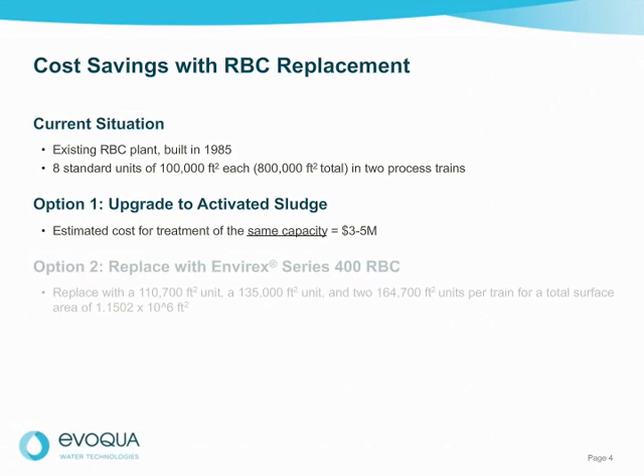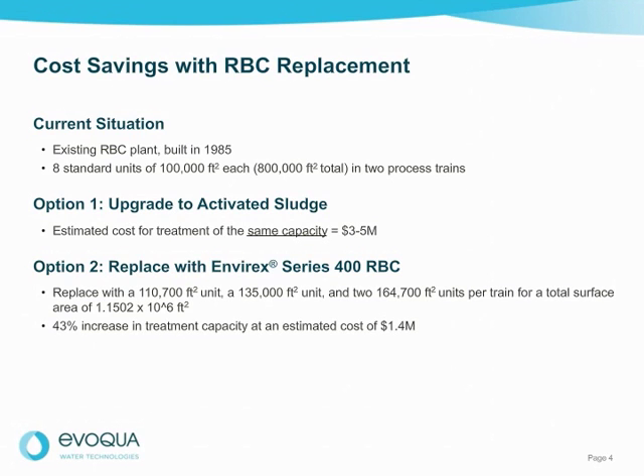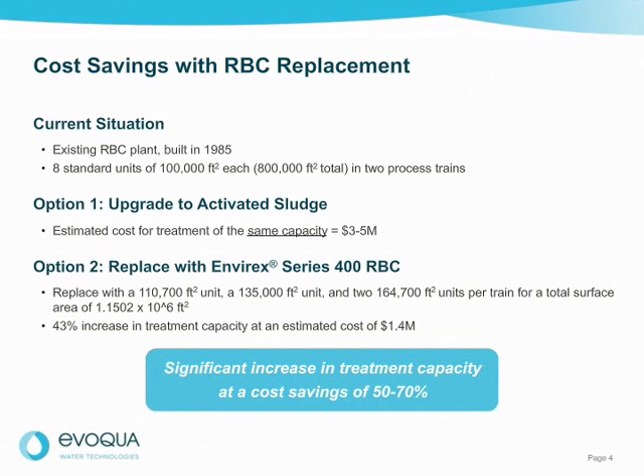Alternatively, Evoqua can replace the two trains of standard density units with the Envirex Series 400 RBCs, consisting of one 110,700 square foot standard density unit, one 135,000 square foot medium density unit, and two 164,700 square foot high density units in each train. The total installed surface area is now 1,150,200 square feet — a 43% increase in treatment capacity without the need to add additional equipment or concrete tankage. The estimated equipment cost for this option is about 1.4 million dollars, including process verification and engineering, resulting in a cost savings of 50 to 70 percent over an activated sludge system.